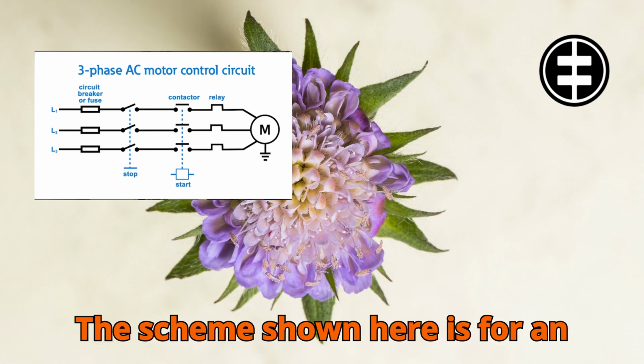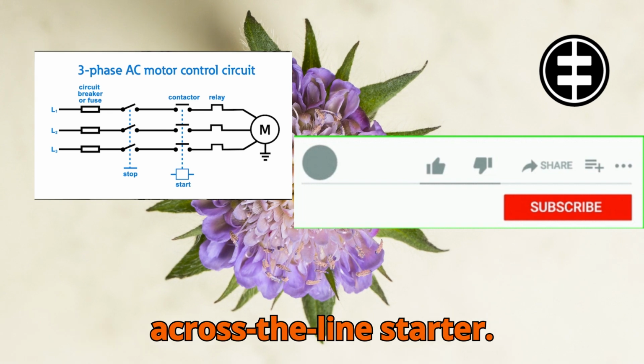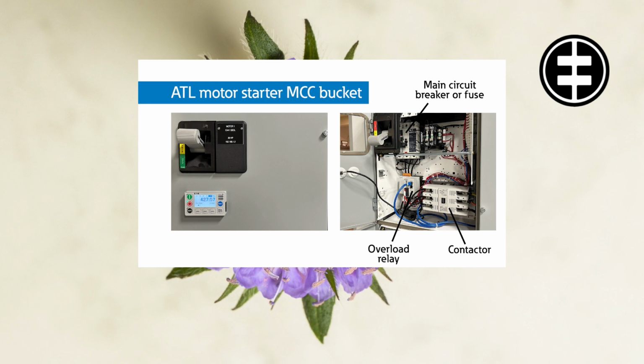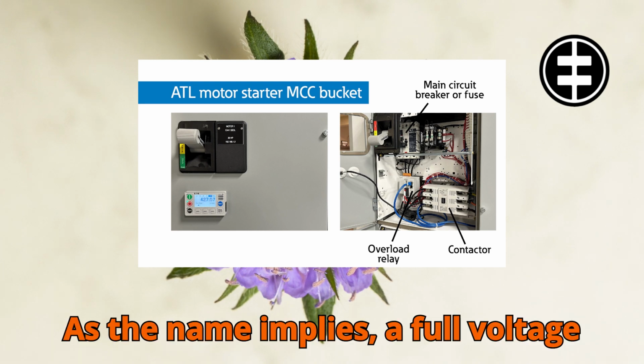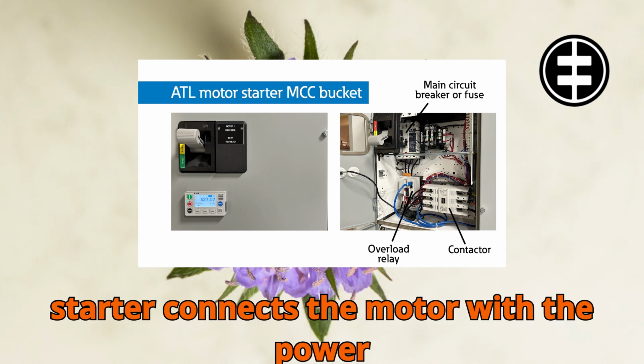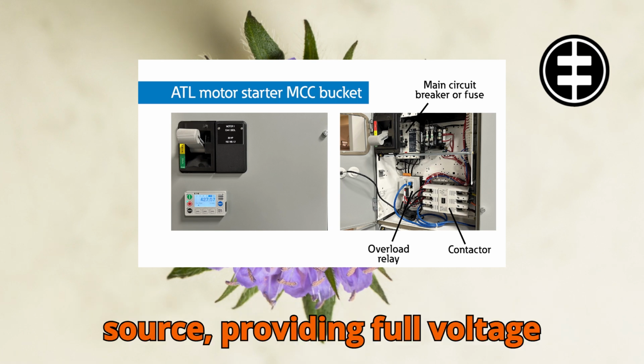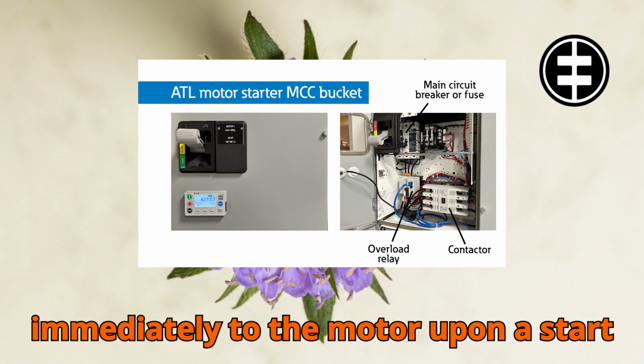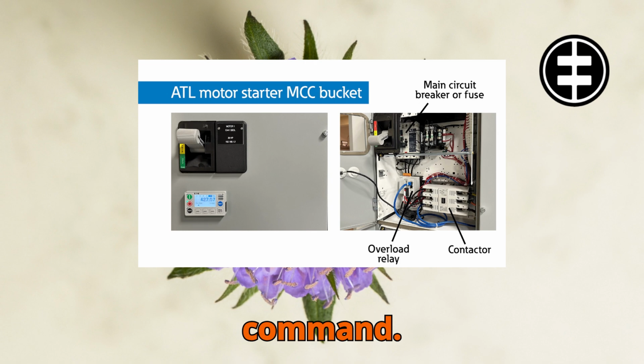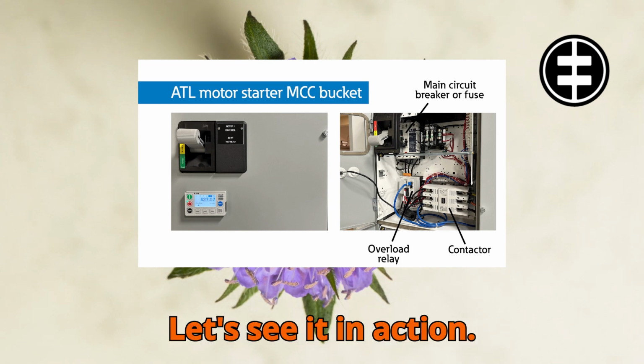The scheme shown here is for an across-the-line starter. This may also be referred to as a full-voltage starter. As the name implies, a full-voltage starter connects the motor with the power source, providing full voltage immediately to the motor upon a start command. Let's see it in action.